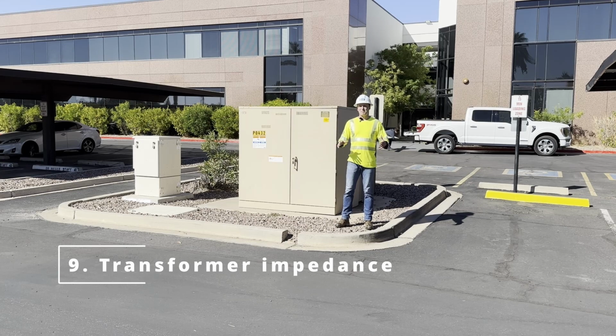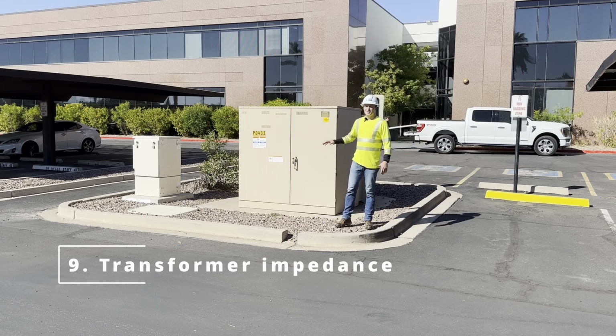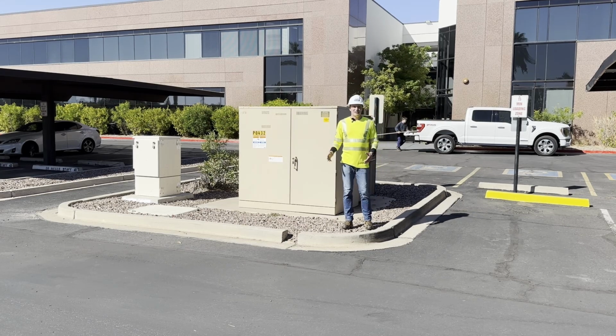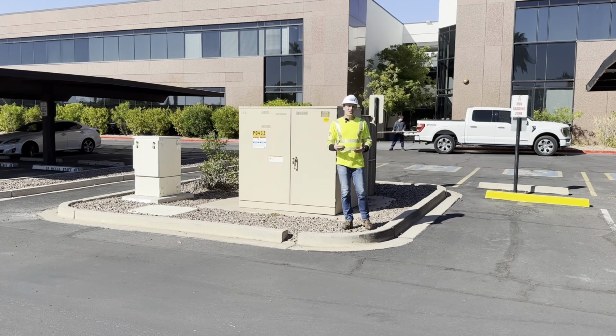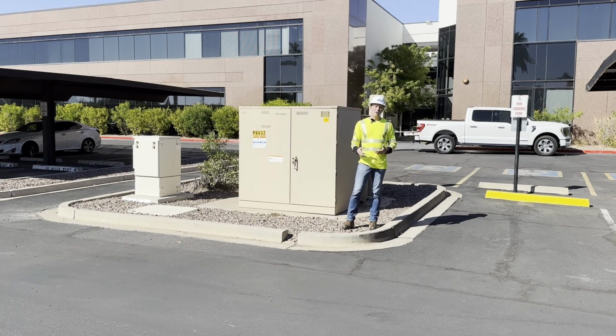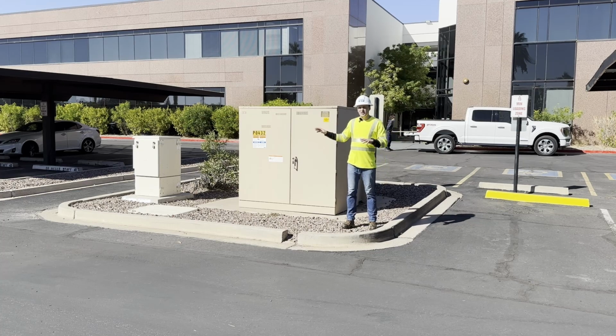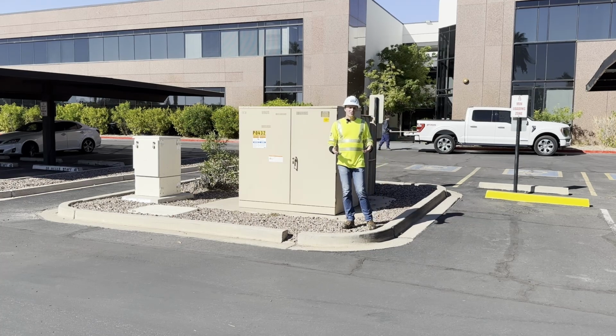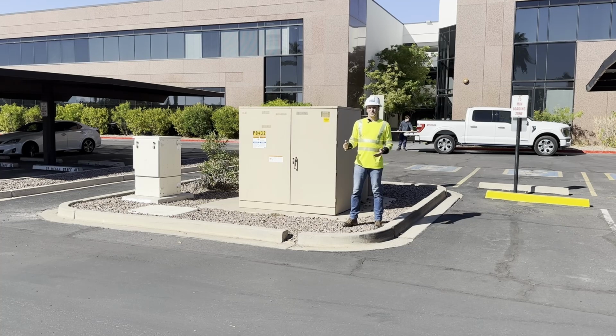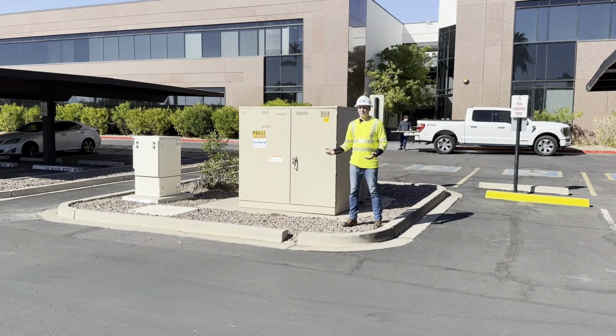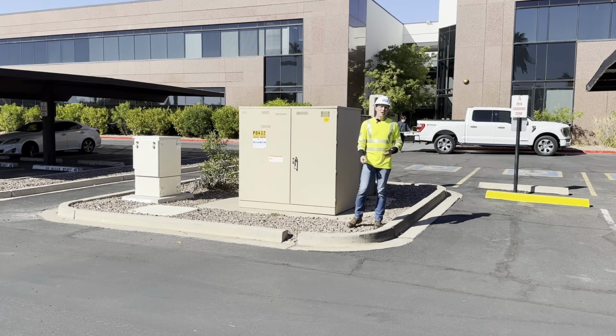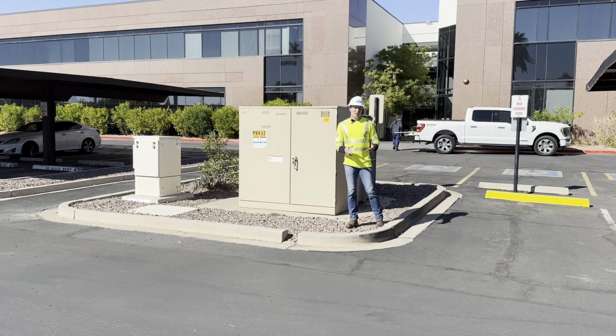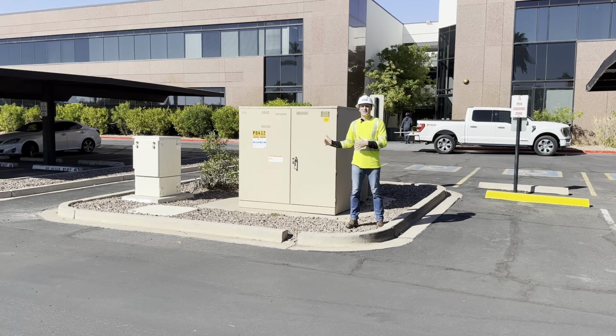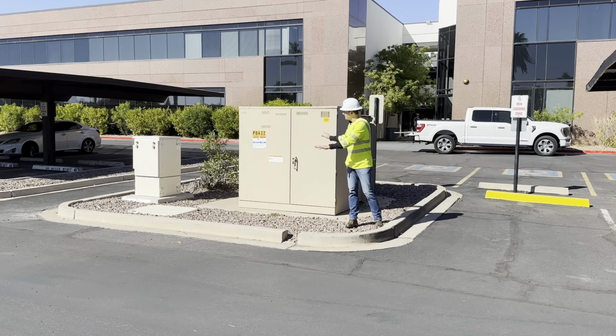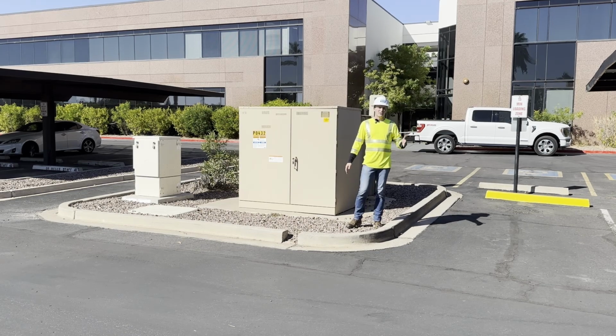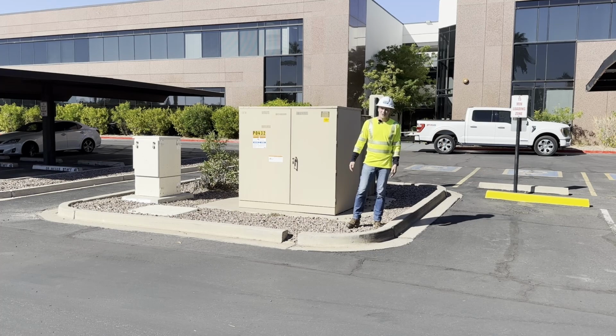Number 9: impedance of transformers. Transformers aren't perfect conductors of electricity—there's some resistance to current flow through them. For most secondary services, utilities will have between 5 and 6% impedance on their transformers. This is important so your engineer of record on the developer side knows how to protect your system if there's ever a failure on the utility side, catching the fault before it goes further into your system.